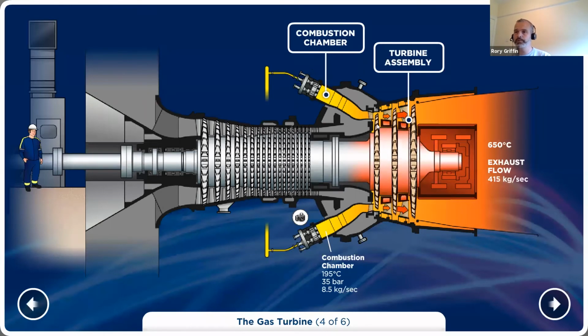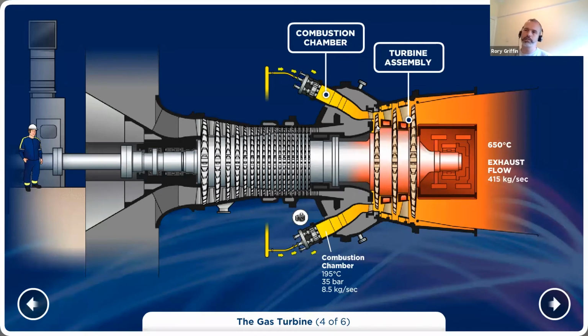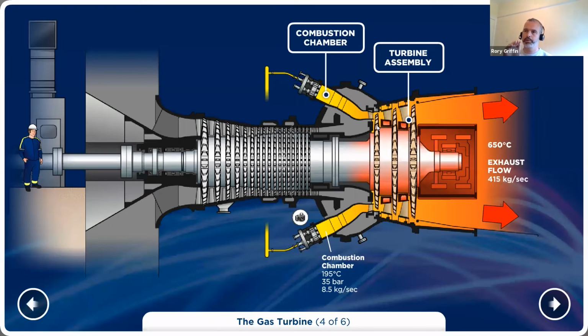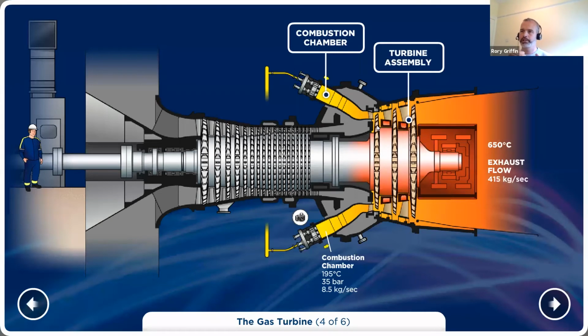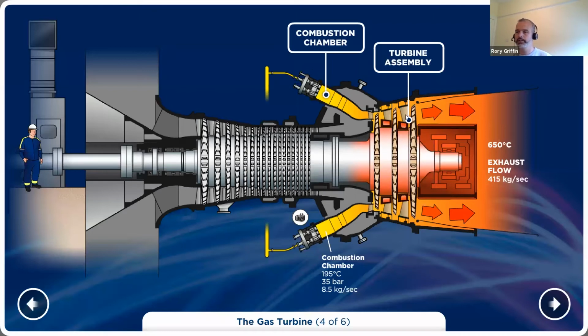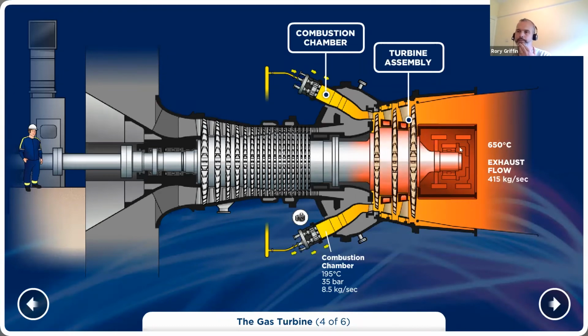So as you get from the first stage, same idea again as the compressor, it'll go past the blade. GE call the blades buckets because, I suppose, a bit like a more pronounced aerofoil pattern on it. It's designed to capture the hot gas and get a rotation. So again, it'll go through a nozzle, straighten up, hit the next set of blades, rotate again, the next nozzle, and finally after the third stage, it's out into the exhaust. Now bear in mind, we've had 1400, maybe 1420 degrees here, and we're down to 650. So it's quite a drastic drop in temperature. So that's really the energy conversion. Here's what you're seeing through the heat loss.